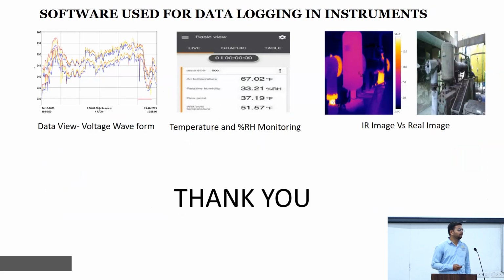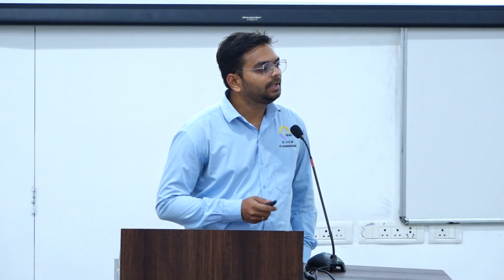These are the softwares we are using, because all meters have data logging facilities. To utilize the data logging facilities, as well as for the analysis of the recorded data, we are using this software for power quality analysis. There is the data view software to measure the waveforms, analyze the recorded data, and monitor the dips as well as the swells in the system. Then for temperature and RH monitoring, we use this instrument for continuous monitoring, and we can record the data also.